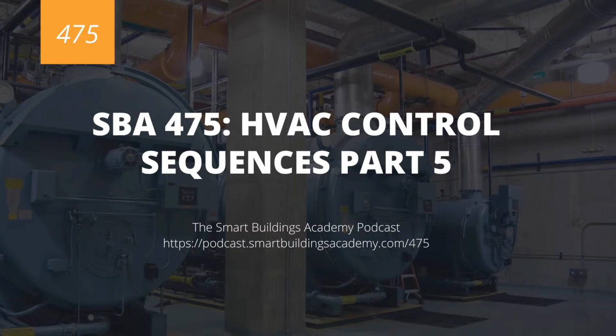But here's the deal. When we're working with boilers, I want you to remember this as we move into our hot water control. You need to be cognizant of several different constraints. You have minimum outlet temperatures and maximum outlet temperatures. You need to maintain a temperature drop across the supply and return. We'll talk about why later. You'll need to slowly warm up boilers, and this is going to affect secondary control, morning warm up, multiple boiler setups, running things in unison, and doing lead lag with peak control.